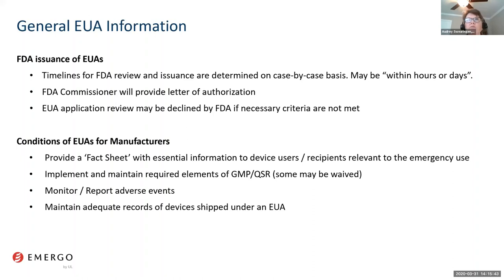Additional general information. The FDA will review and issue an EUA on a case-by-case basis, heavily dependent, of course, on the priority of the need and of the device in question. The FDA will issue a letter of authorization, and of course, they may decline reviewing or issuing an EUA if the necessary criteria are not met. There is certain information and there are conditions that manufacturers need to meet under an EUA. So they have to provide essential information to the users or recipients of the device. They have to implement and maintain required elements of good manufacturing practice or quality system regulation, unless it's waived by the FDA. They must monitor and report adverse events and maintain adequate records of those devices that are shipped under the EUA. And they have to make those available to the FDA upon request. Next, please.